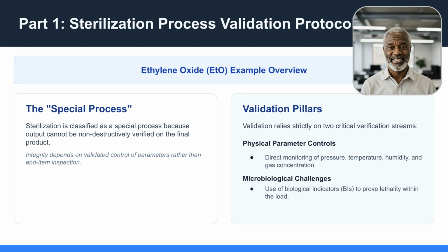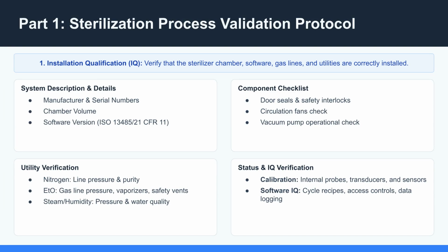Sterilization is a special process because its output cannot be non-destructively verified. Validation relies on 2 verification streams: physical parameter controls like temperature and gas concentration, and microbiological challenges using biological indicators to prove lethality.